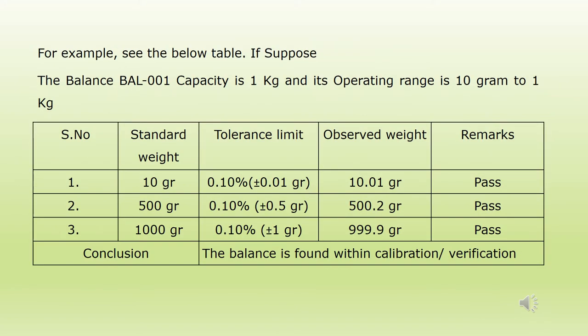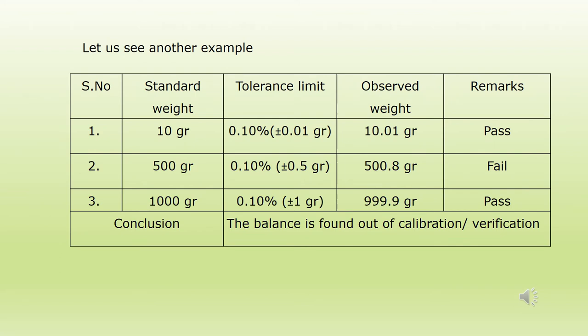For example, if the balance capacity is 1 kg and its operating range is 10 grams to 1 kg, and it is calibrated using 10 grams, 500 grams, and 1000 grams, and the observed weights are within the tolerance limit, the balance is said to be calibrated or verified successfully. If the observed results are out of the tolerance limit, the balance is said to be out of calibration for daily verification.